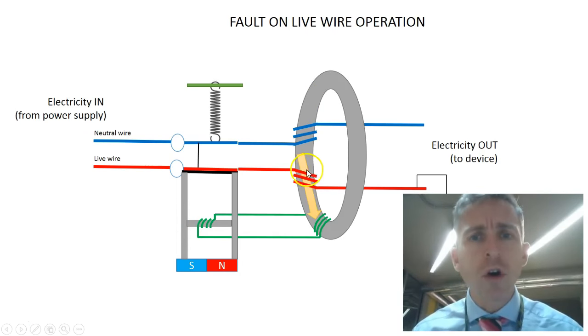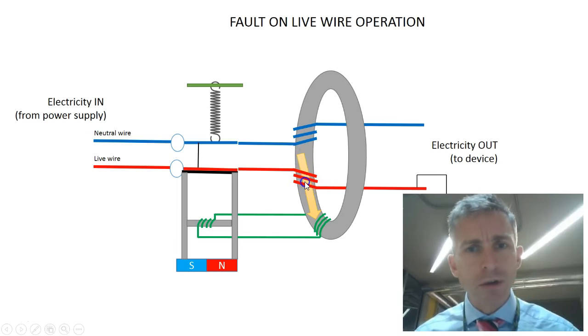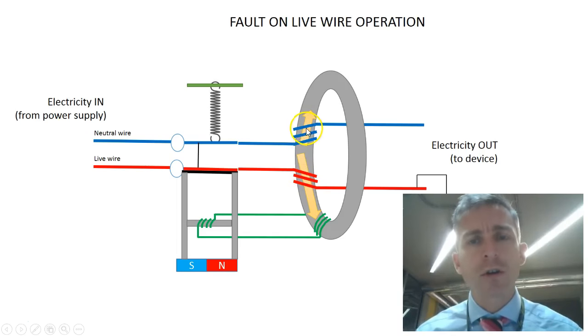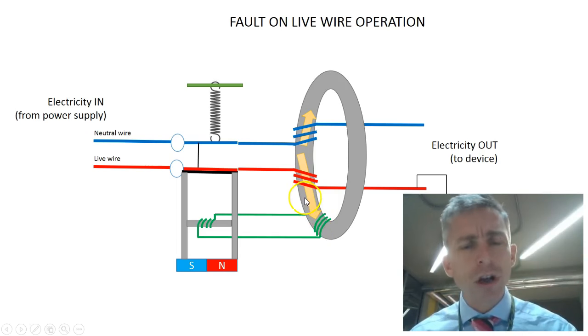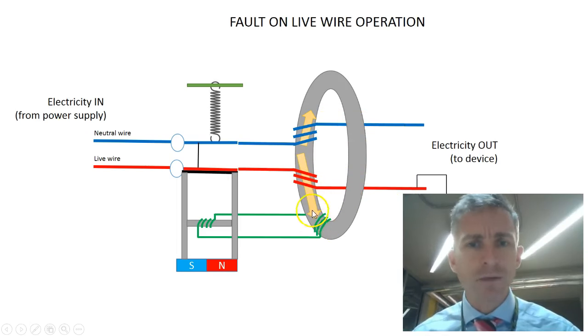However, if there is something wrong, then the current supplied is greater than the current that returns. And that means that there is a greater magnetic field here than here. And so you end up with a net magnetic field. A net magnetic field will produce a voltage across this coil. And it does so because these are actually alternating currents. And the changing magnetic field induces a changing alternating current inside this coil.